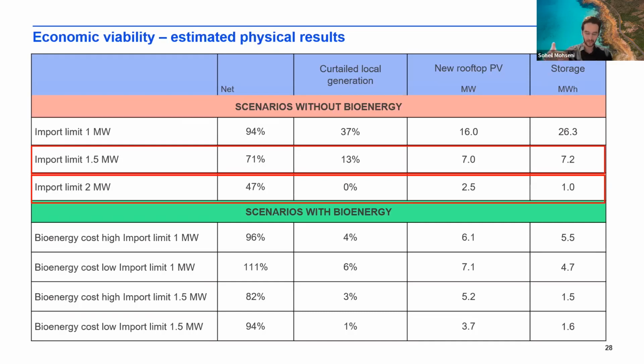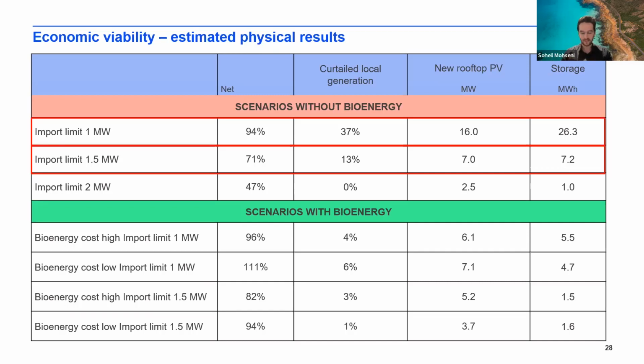So if we lower the import limit to 1.5 megawatts, that gives us a local supply of 71%. Well, that's better, but probably it's not enough. So let's reduce the import limit further down to 1 megawatt. And that gives us a local supply of 94%. But that comes at the cost of curtailing 37% of local generation, because we have an export limit of 1.7 megawatts. And in this scenario, we also need to install 16 megawatts of new rooftop PV and 26 megawatt hours of new storage, which makes this scenario very costly indeed.